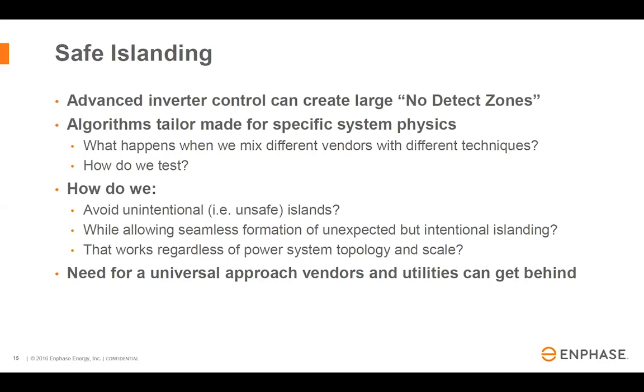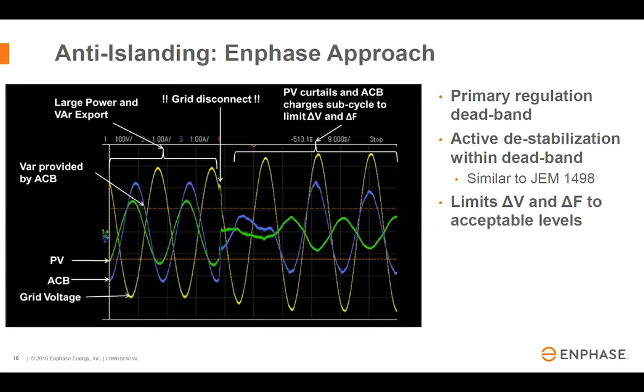from the distribution end. Our approach has, and by the way, this is not what we invented, I first read about this in a paper in 2006. But the idea here is you create sort of this dynamic deadband that runs at a much higher bandwidth than your other controls. And in that deadband, you run a destabilizing control. We're using a technique very similar to what's described in JEM 1498, where they actually control VAR injection based on frequency deviation.